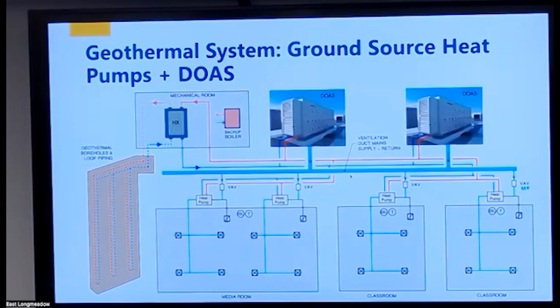We'd have a network of vertical boreholes drilled about 500 feet down, each with a pair of pipes, linked together and brought into a mechanical room. Water is pumped out to the various heat pumps serving the classrooms, media center, guidance, admin, and other spaces. It's basically a network of water pipes providing heat exchange between the individual heat pumps and the earth.